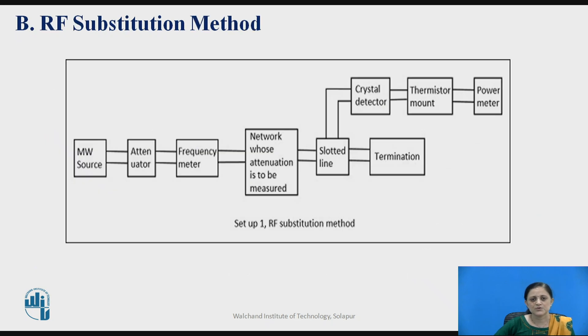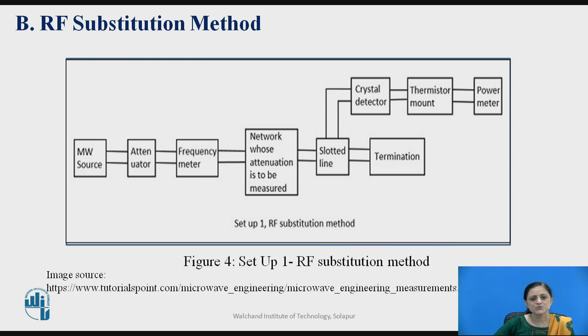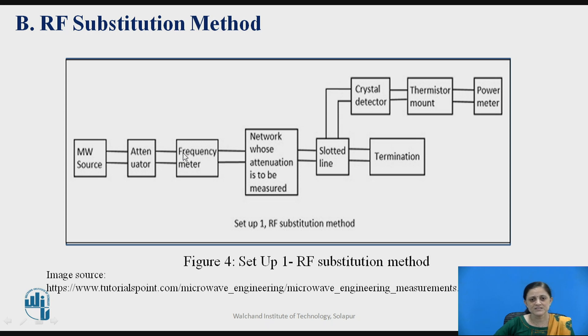This drawback of the power ratio method can be eliminated using the RF substitution method. In RF substitution method Setup 1, the same block diagram is used: microwave source connected to the attenuator, then to the frequency meter, then to the network whose attenuation is to be measured, and then to the slotted line section. The power meter reading from this setup is noted as P.